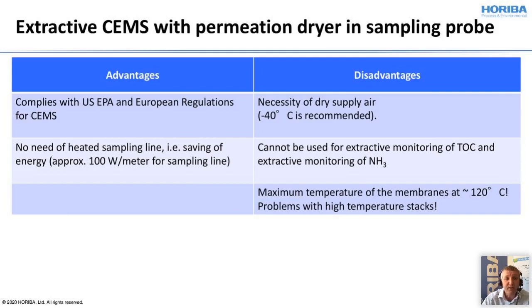The big disadvantage is that at the sampling probe you need dry supply air, which is normally instrument air, oil and water free. You need to bring it there. And also the consumption of this dry supply air is sometimes quite high. The biggest disadvantage in our case is that the membranes will only stand a maximum temperature of 120 degrees C. So if there is a high temperature of the gas in the stack, we need to find another solution because the membranes will melt and your probe and your cooler are damaged.